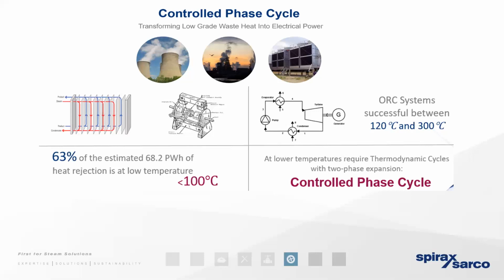So if we look at a traditional organic Rankine cycle, that's traditionally going to recover the heat that's available, but only when it's in excess of 120 degrees. So the modern innovative controlled phase cycle, or CPC, can now make use of the heat energy that is going to exist at significantly lower temperatures. We can take waste heat from temperatures as low as 70 degrees, but obviously the higher the waste temperature stream, the greater those returns are going to be.